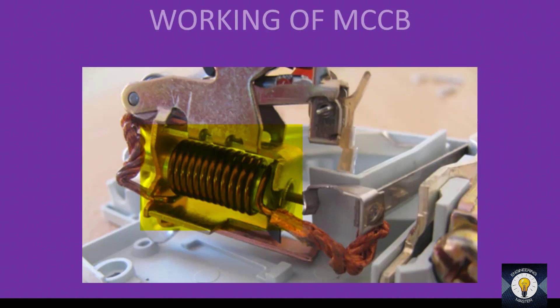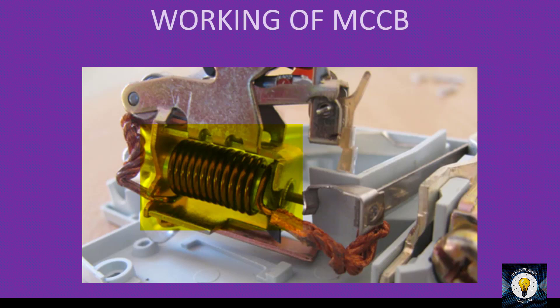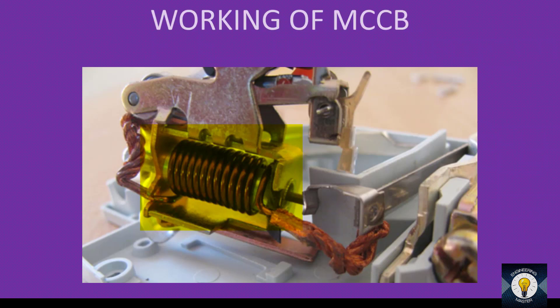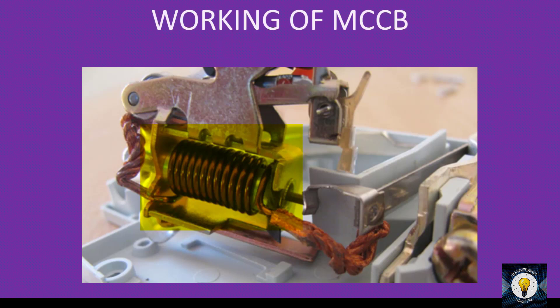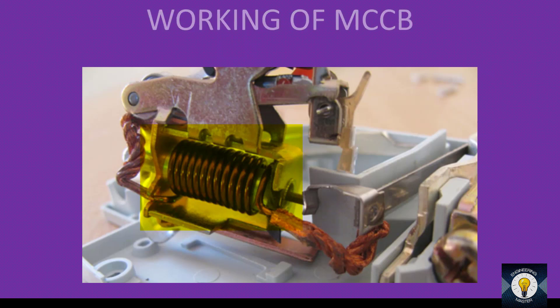In normal current conditions there is also a magnetic field with some chance of tripping, but a spring is present and its tension holds the piston back. If the current exceeds a certain level, the magnetic force becomes greater than the spring tension, and the piston trips the mechanism.